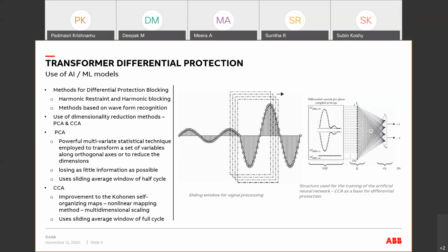There is an additional fifth harmonic restraint which will be included in the relay, and the waveform recognition algorithms are used to distinguish the faults from inrush to improve the relay performance. Now let us look at the newer alternatives. Till now we were discussing the traditional alternatives.